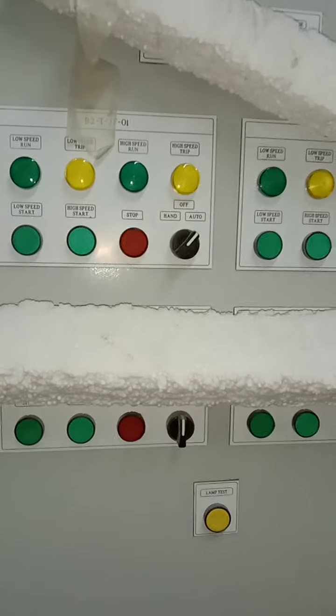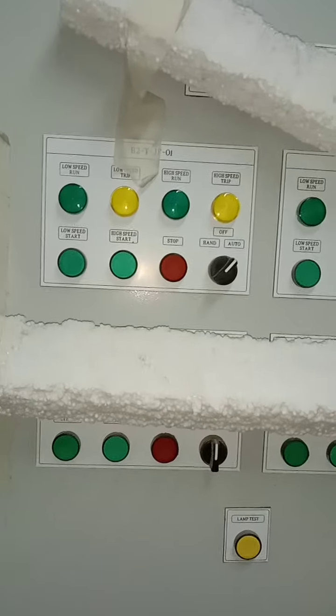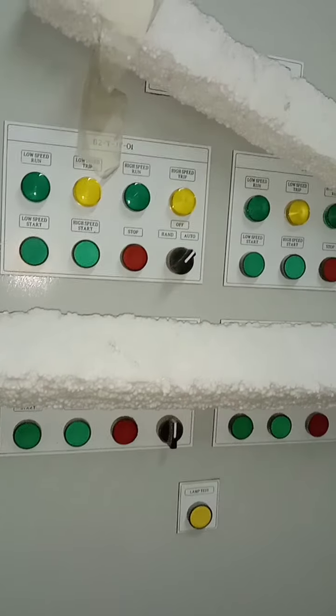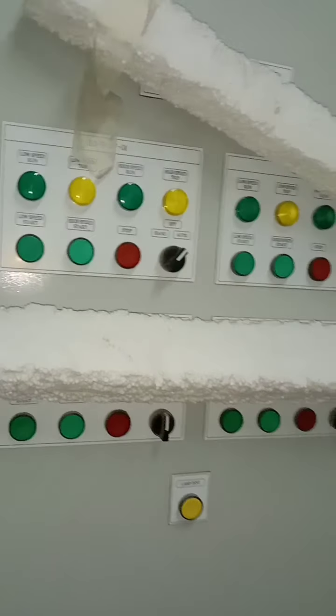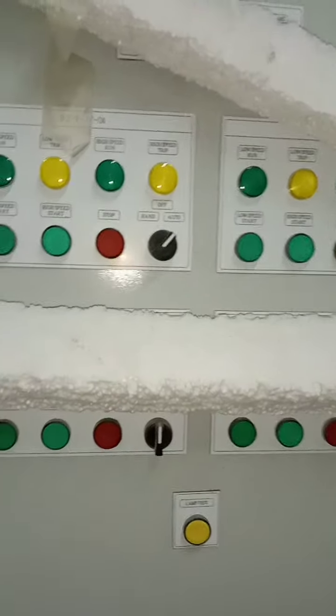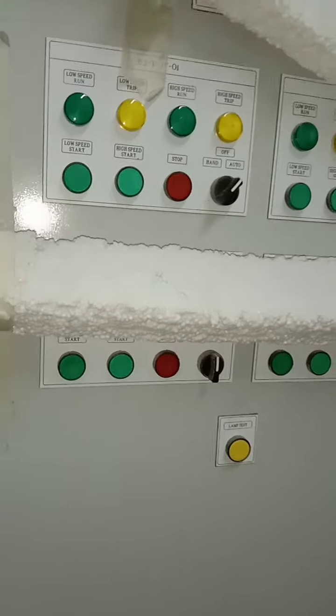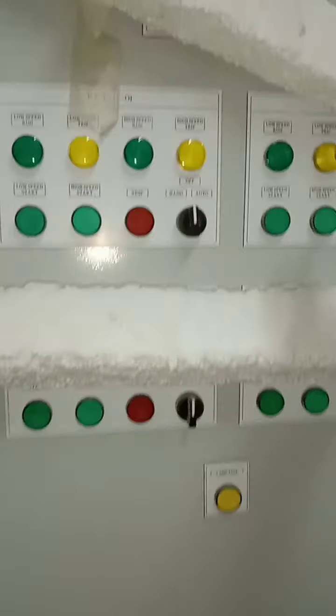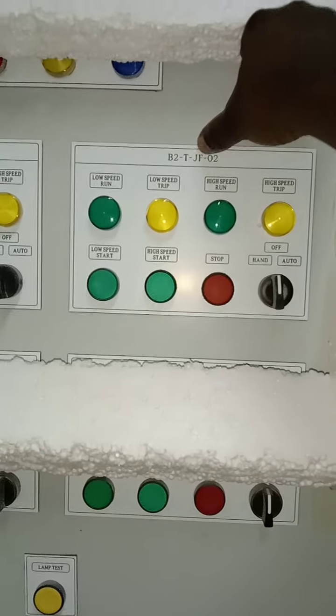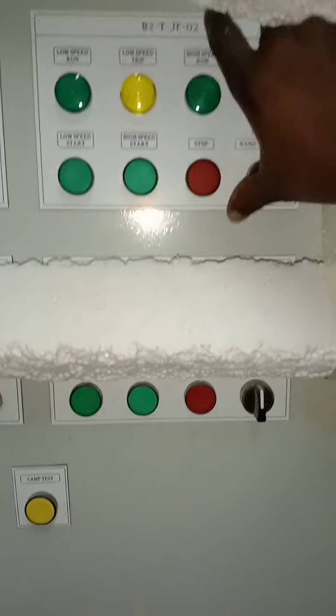And then in the case of a fire condition, that is if the fans are off, they will turn on automatically in order to push out the smoke in this room and then send it outside. I'll put it at off now. The next will be for B2TJF2, that is the number 2 jet fan. The third jet fan, the fourth jet fan, and so on up to the ninth. So this panel is feeding 9 jet fans.